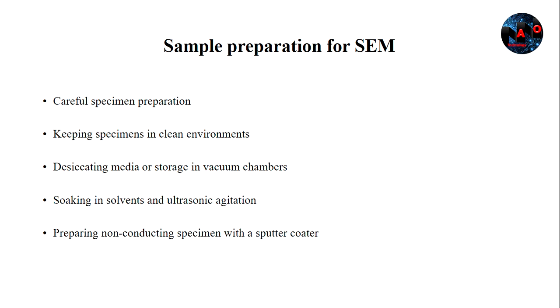Because metals already conduct electricity when bombarded with electrons, they do not require any preparation. However, non-metals need to be prepared with a sputter coater. The specimen is provided with a thin conducting material layer, usually gold.